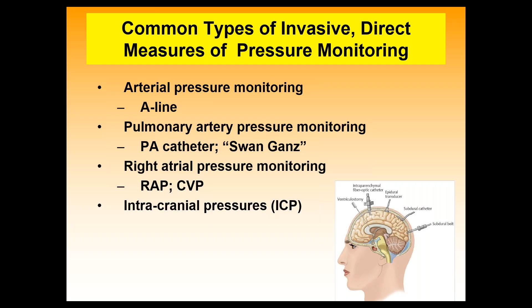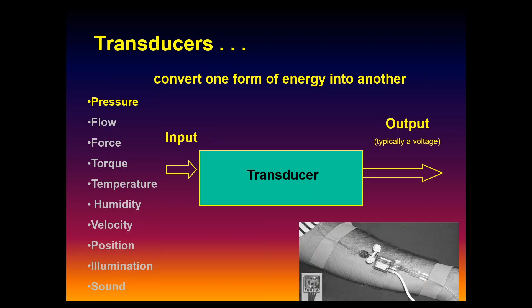But they all use the same transducer, whether you're measuring intracranial pressure, we're measuring pressure. And to measure pressure, we use transducers. And just like all of our other transducers, it converts basically one form of energy into another. All transducers behave essentially that way. Regardless of what the input might be, we can virtually measure most anything out there. And our outputs of these transducers are typically, not always, but more often than not, voltages that correspond to the input value. And the good transducers, they're virtually perfect in that regard. Correlations are almost 1.0, very linear, very repeatable devices, the good ones are.